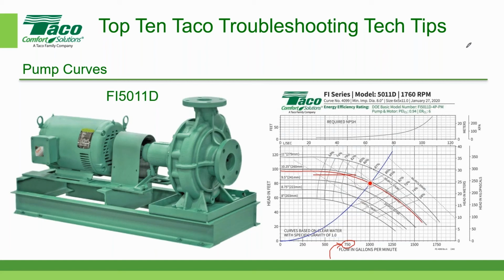So I'm going to go over here and get another pen. I'm going to draw another system curve. Now, in this particular case, I'm going to draw a system curve from here. Whoops, didn't do that real good, did I? Let me try this one more time. And start off here, and I want that to go up here. Well, that's not the best system curve in the world. So in reality, it's beginning to look like this is the actual system curve over here and not what they originally designed to. So what could potentially be causing the problem?